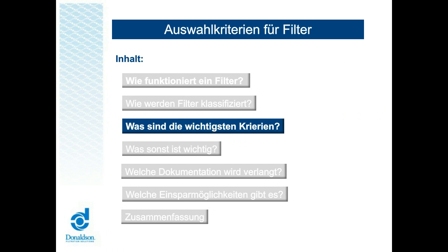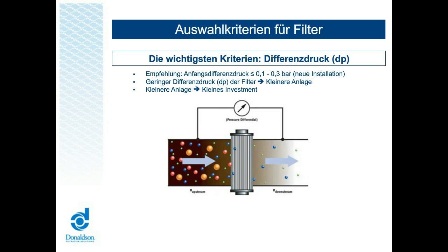Diese Klassifizierung ermöglicht uns einen Einblick in die Aspekte wie Filterleistung, Betriebssicherheit und die Gesamtkosten des jeweiligen Systems — auch Cost of Ownership genannt. Das wichtigste und offensichtlichste Kriterium ist der Druckverlust, der auch als Delta-P oder DP bezeichnet wird. Es ist wichtig zu verstehen, dass jeder Filter unabhängig vom Typ, vom Medium, vom Fluid oder vom Hersteller einen Widerstand im System darstellt, der einen Systemdruckverlust verursacht. Jeder Filter verursacht Gegendruck, was erhöhte Betriebskosten bedeutet. Somit macht es Sinn, den Druckverlust so gering wie möglich zu halten.